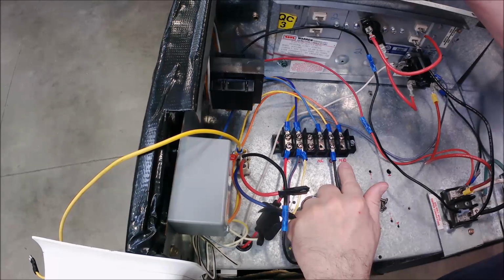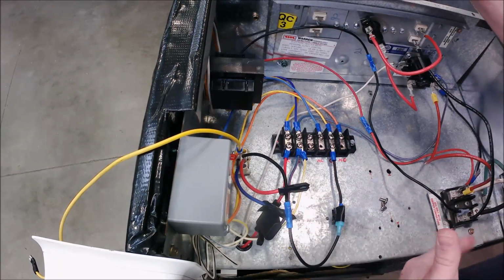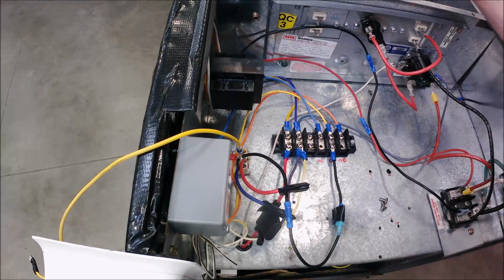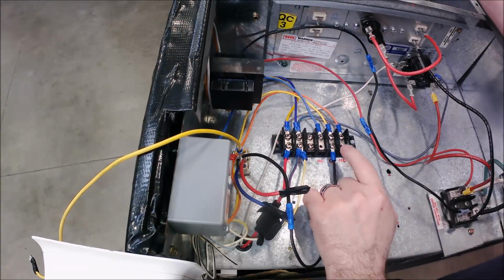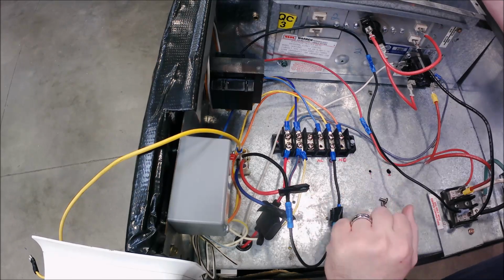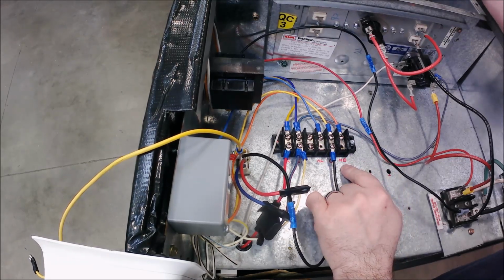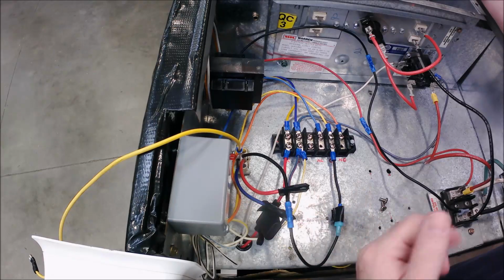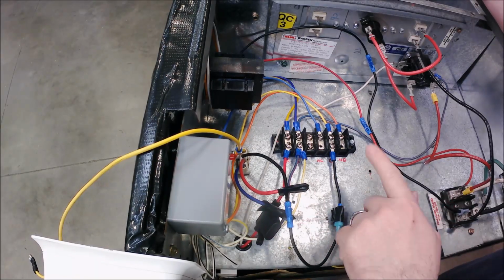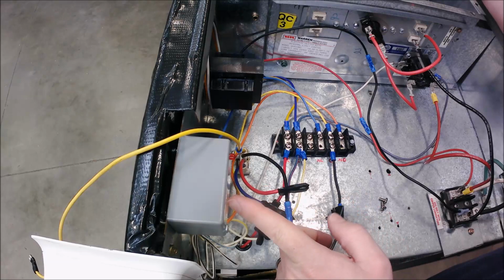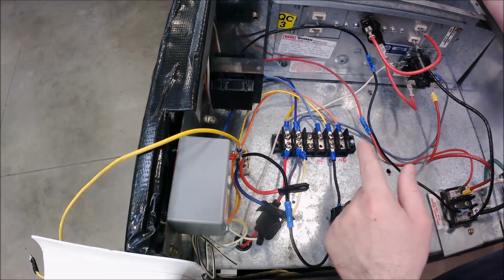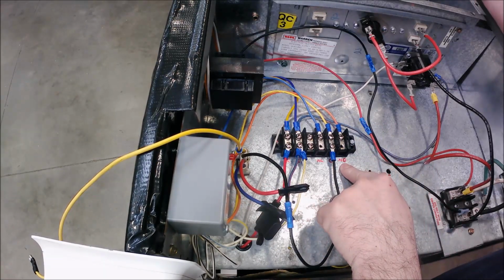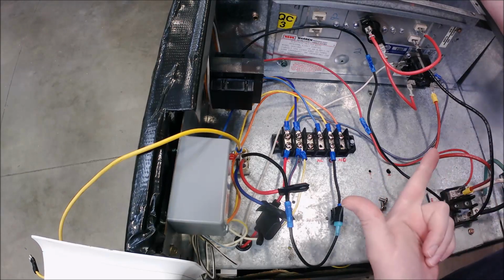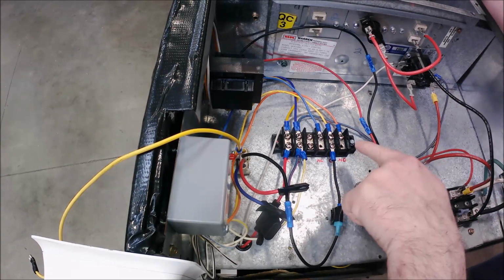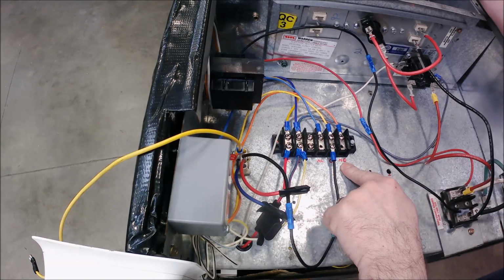So what do we do with normally closed and normally open? Well, normally open is going to be the easy one to address. What we're going to do is normally open only closes, right? We only close that connection to the common terminal when we have a call on the relay for fan or cool. So we have to have an energized coil on this relay in order to use that switch. So we're going to use that in fan mode. We're going to use that in cooling mode. And what I'm going to do here is I'm going to put straight L1 power.